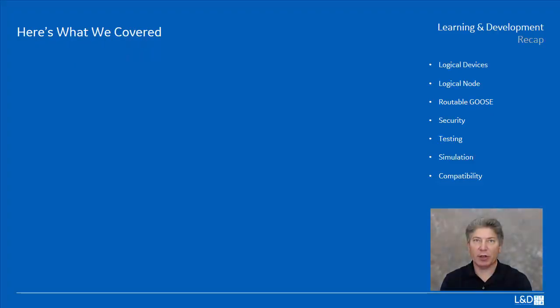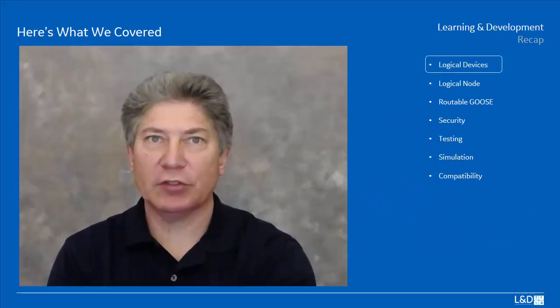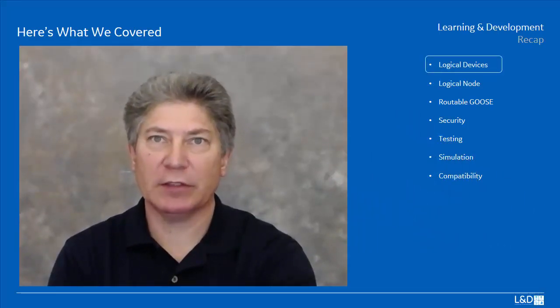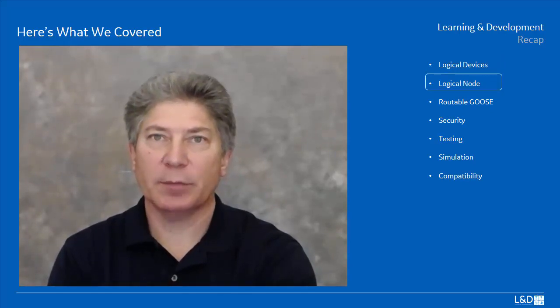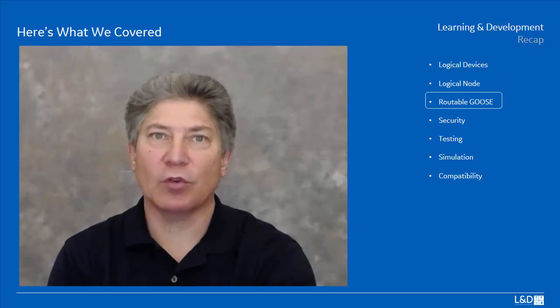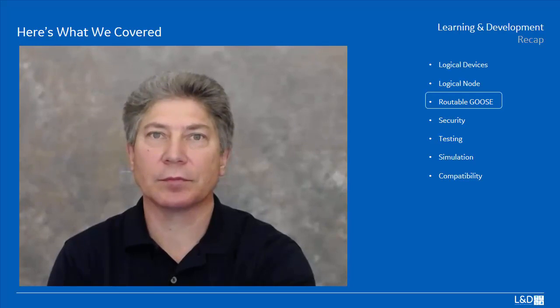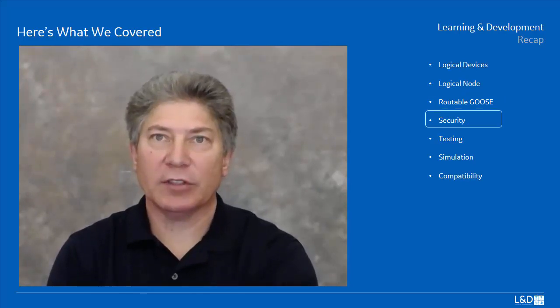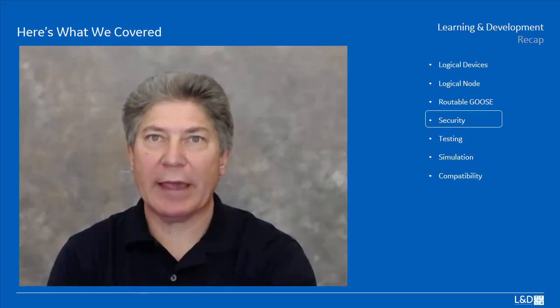Let's recap the material we covered in this module. First, the introduction of logical devices that were specific to a category of operation within the IED. The expansion of logical nodes to cover all function elements of the IED. The introduction of the routable GOOSE, why it was needed, and how it differentiates from the standard GOOSE. Next, we looked at how we maintain security of the routable GOOSE by encapsulating the data into a session protocol data unit and the security of keys, encryption, and authentication of the devices involved.